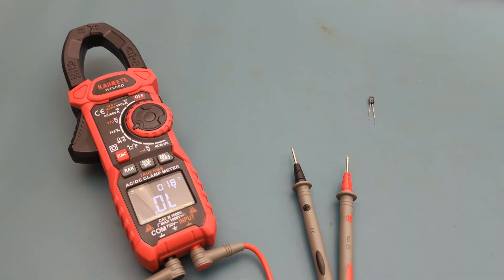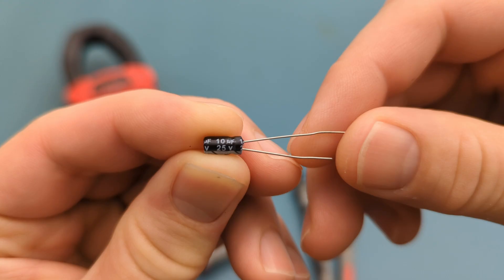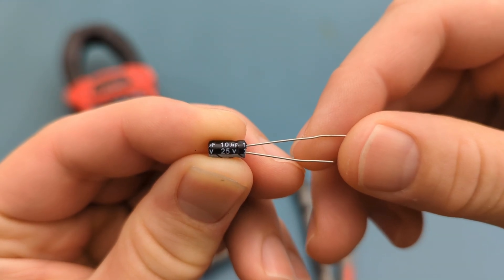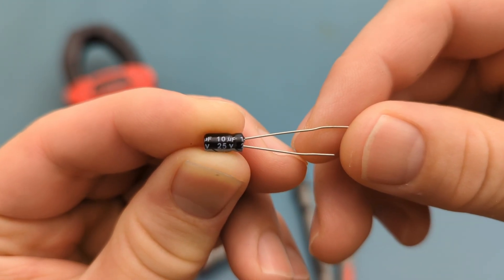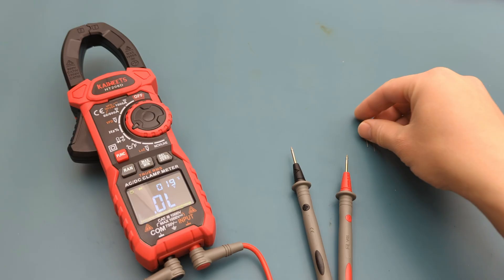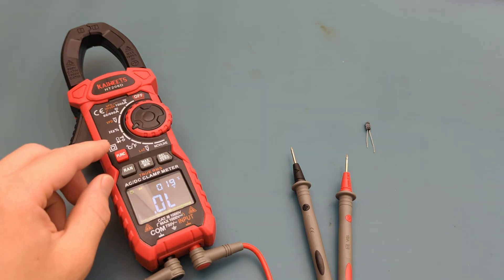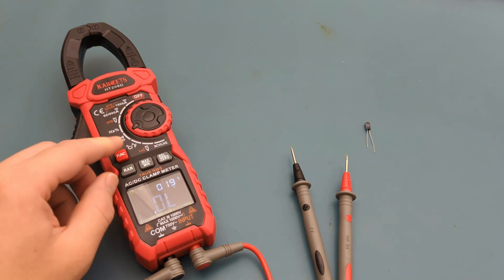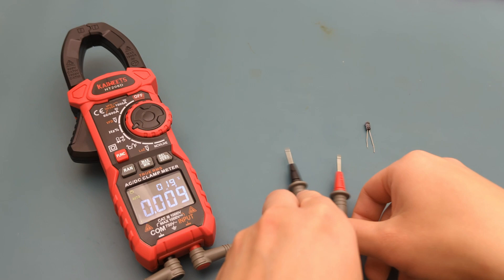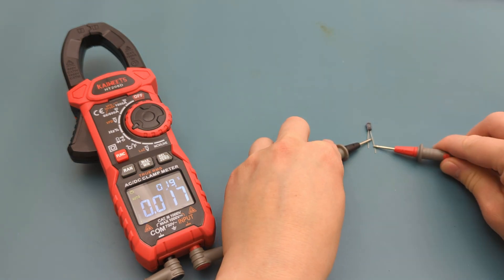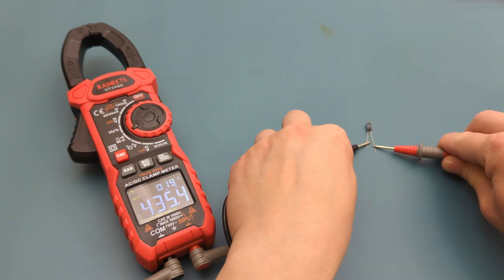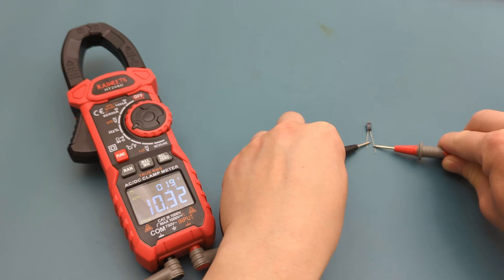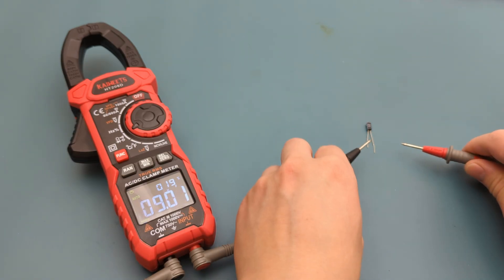The next step is to perform a capacitance test. This capacitor has a capacitance of 10 microfarads. Press the function button to switch to the capacitance setting. When I touch the probe leads to the capacitor, the reading shows around 10 microfarads. The meter takes a few seconds before it shows the reading.